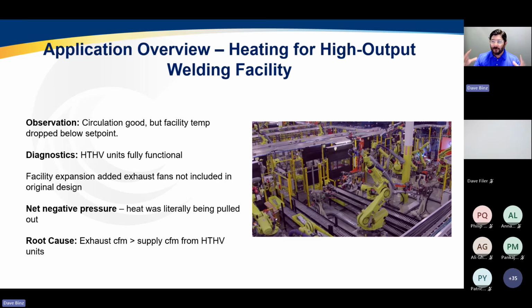This building was actually built with HTHV fully functional to provide the space heating and ventilation for a warehouse. But now that I'm adding so much welding, so much process, we know we have to do something to make sure we're still controlling our indoor air quality. And so they added exhaust fans. That was the first thing they did. They knew they had some welding. They knew they had hoods. They knew they had exhaust to make sure of indoor air quality.